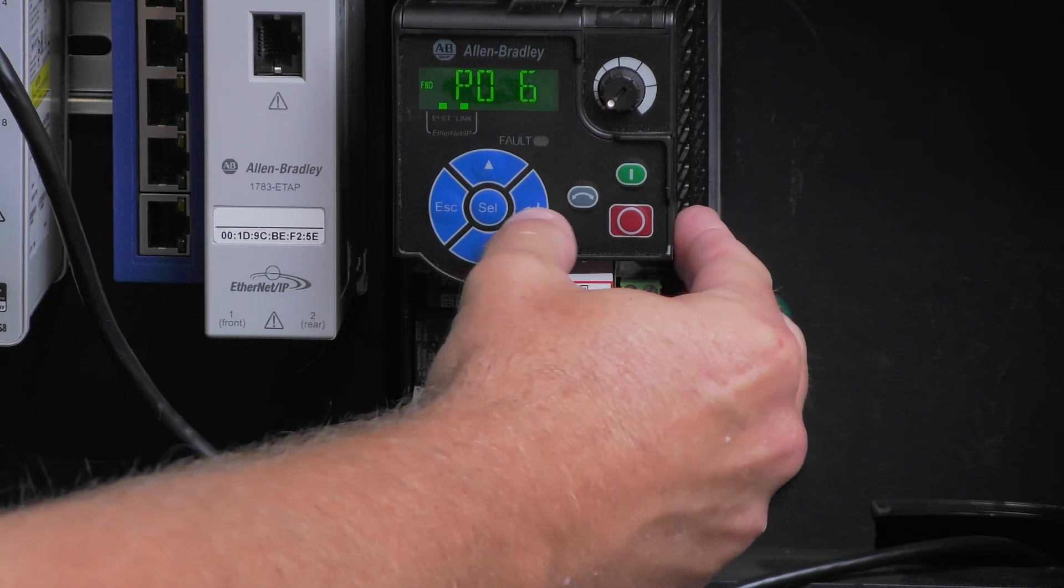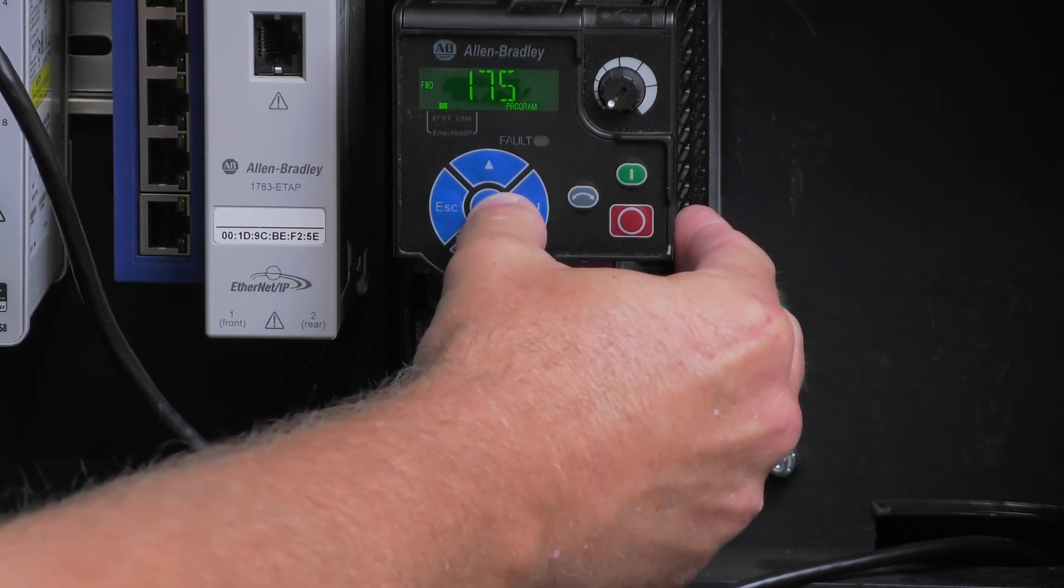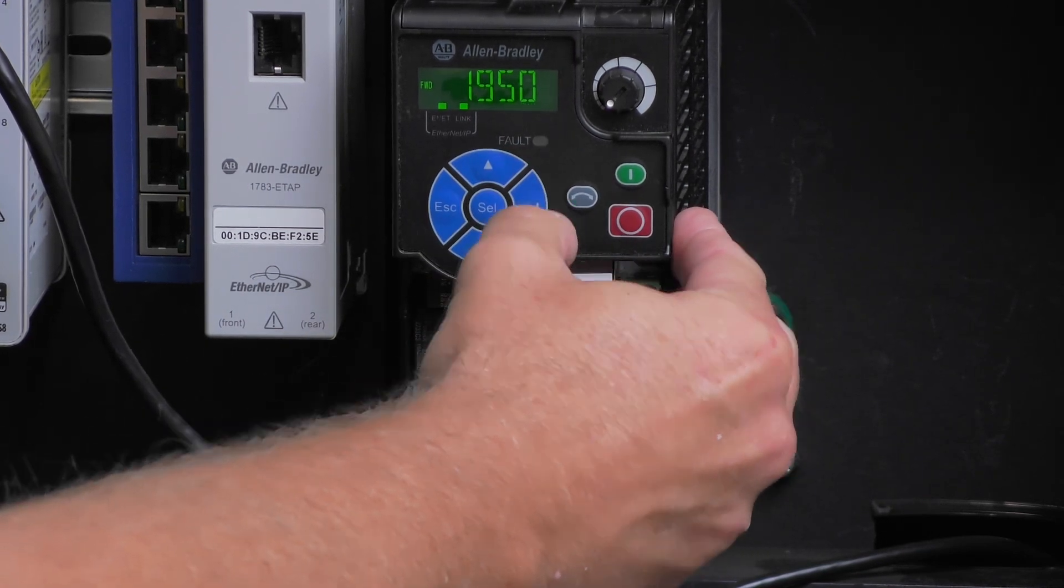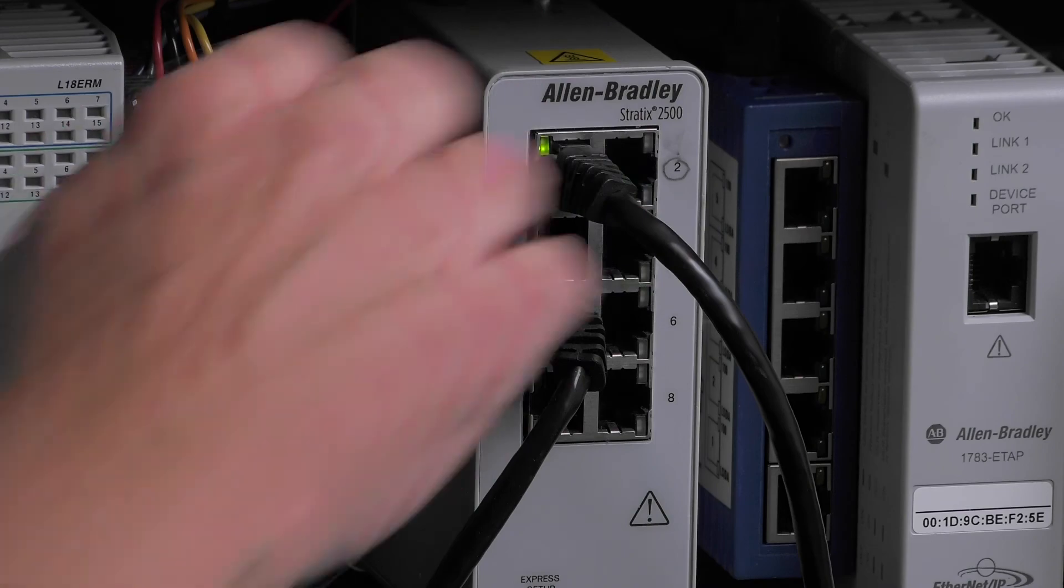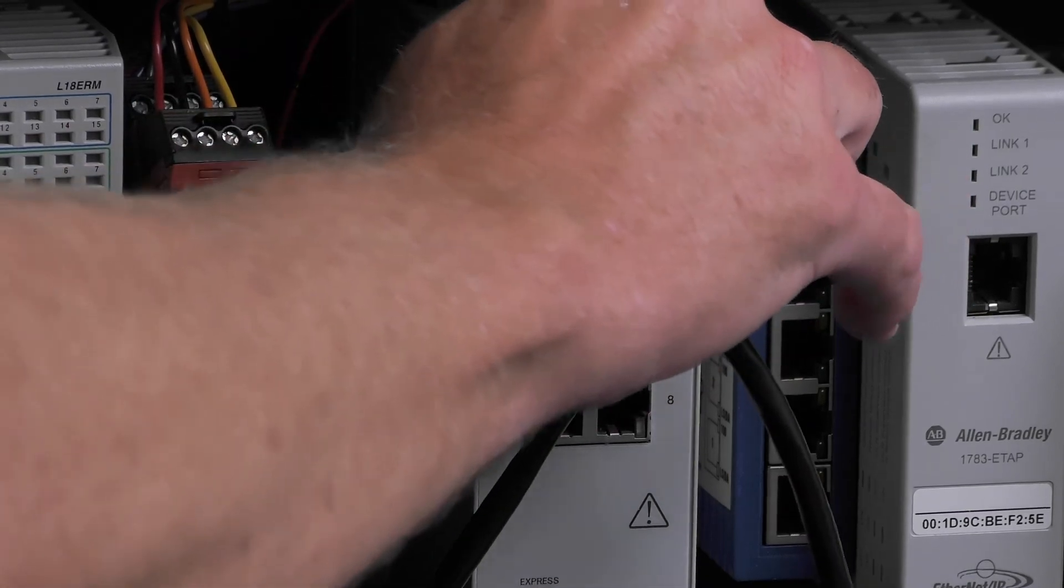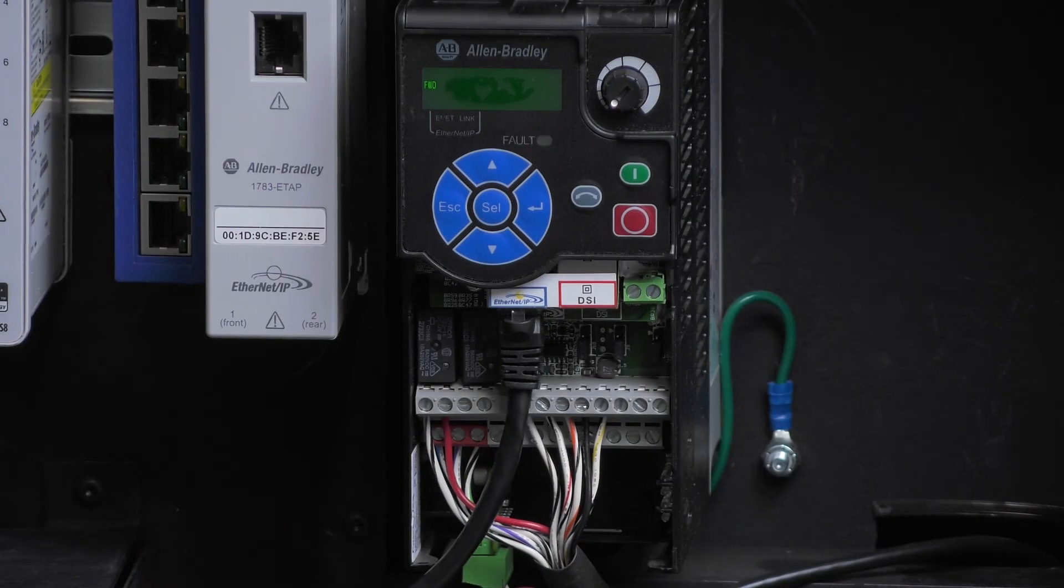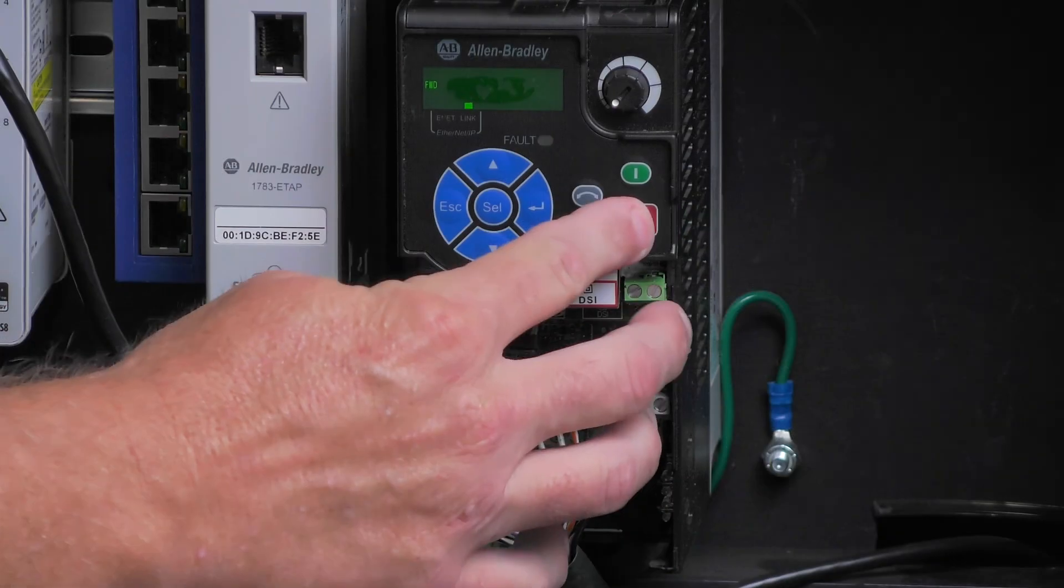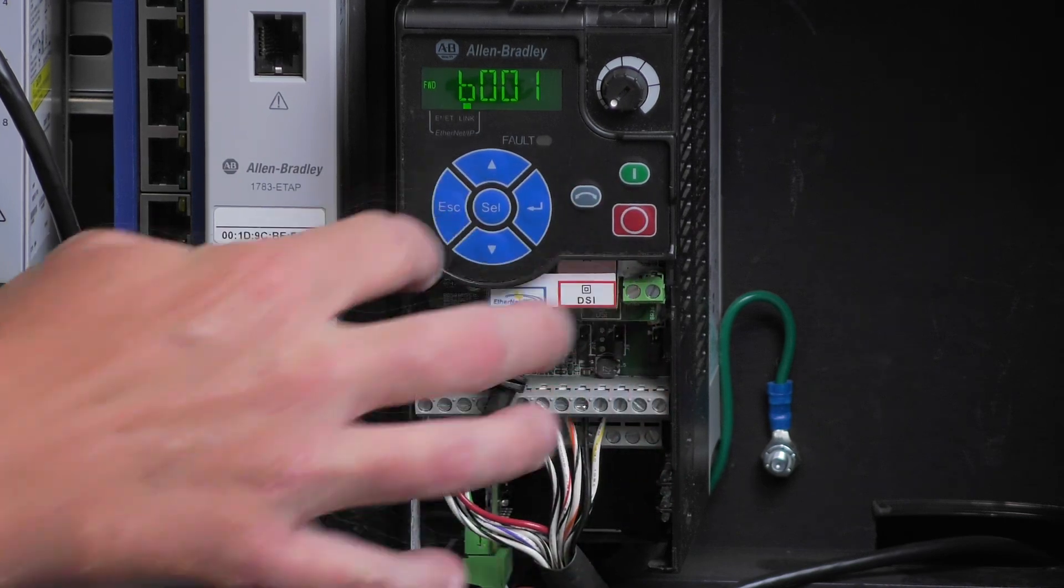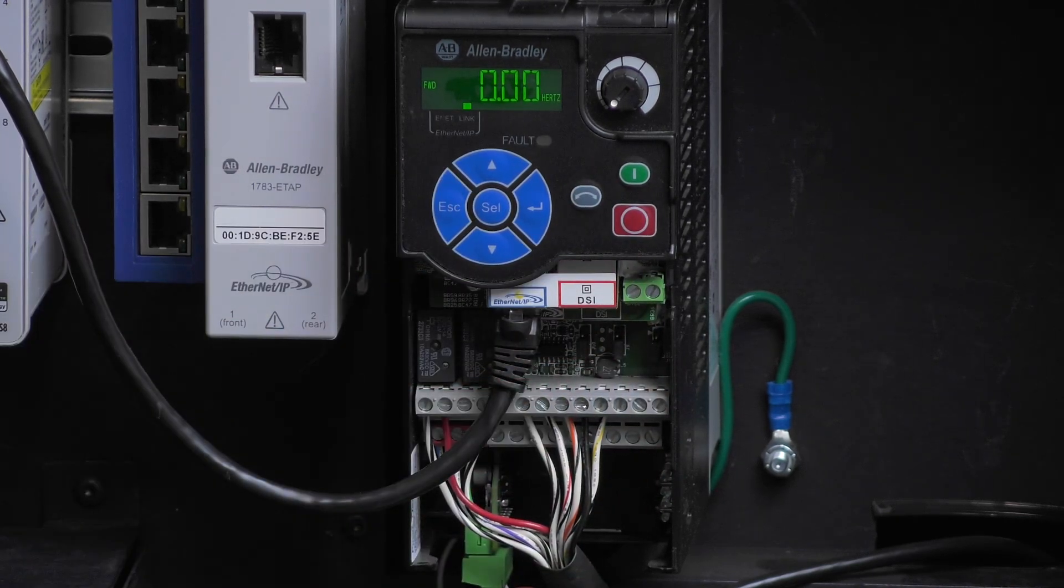We can show that the drive is running. Then we can adjust the motor RPM parameter P36 to 1950 from 1750. The drive will keep that configuration until we disconnect the ethernet cable, which will fault the drive. Once we plug the ethernet cable back in, the fault will clear and show ADC is active. This will return the value back to 1750, and the system can be restarted back to run.